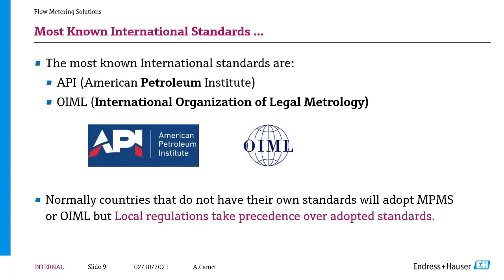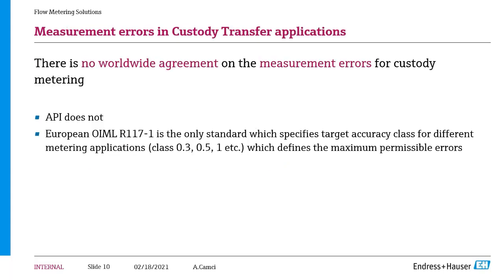When it comes to errors in custody transfer applications, there is no worldwide agreement on measurement errors. API does not state a figure for the measurement error. The European OIML R117, measurement of liquids other than water, is the only standard which specifies a target accuracy class for different metering applications, like class 0.3, 0.5, 1. For example, class 0.3 is for pipeline metering, 0.5 for truck loading or bunker measurement, or 1% for LPG and such other applications. And these numbers define the maximum permissible errors.